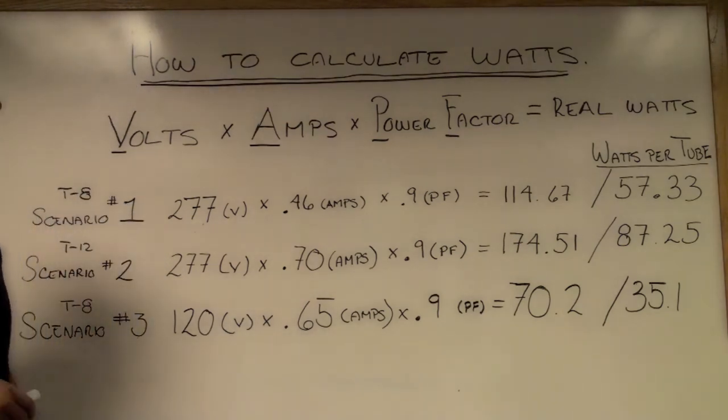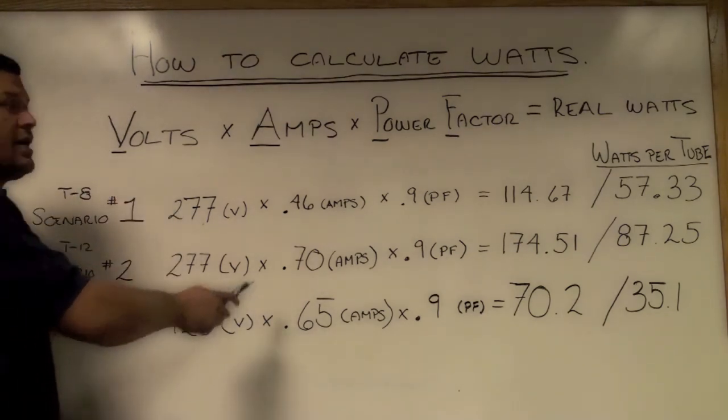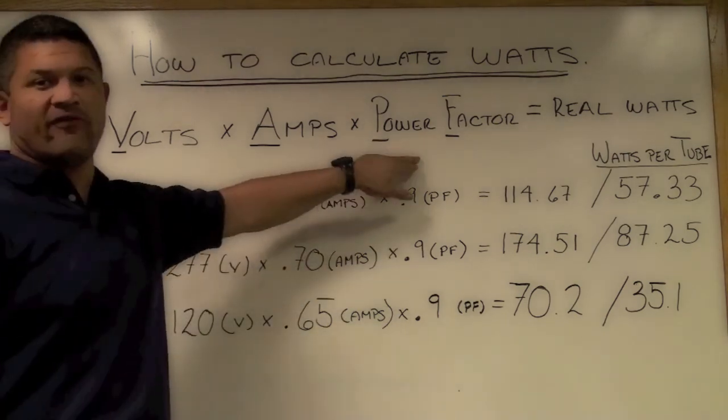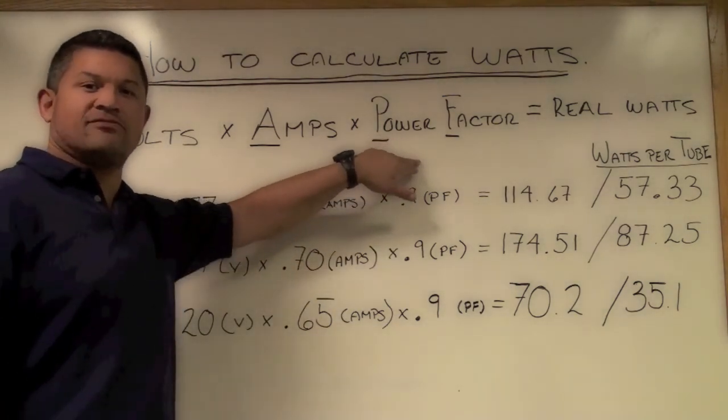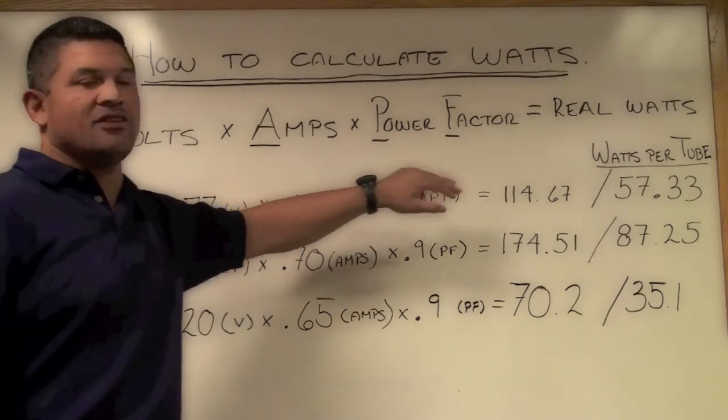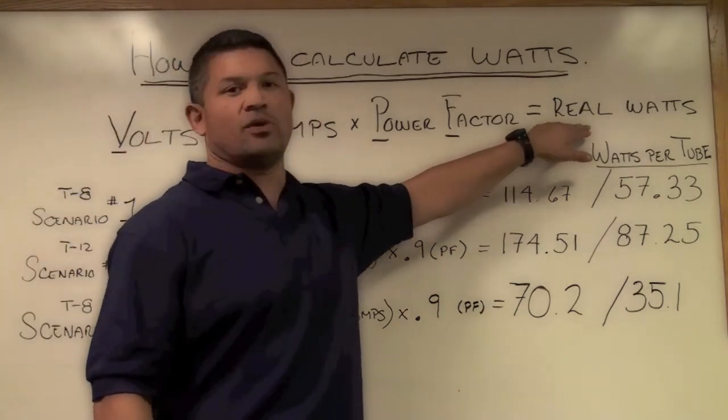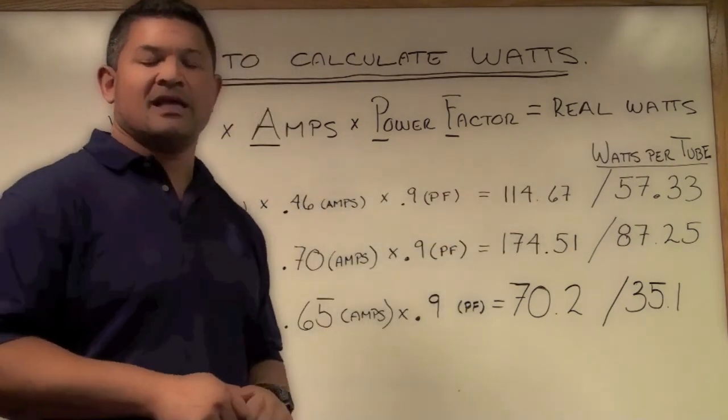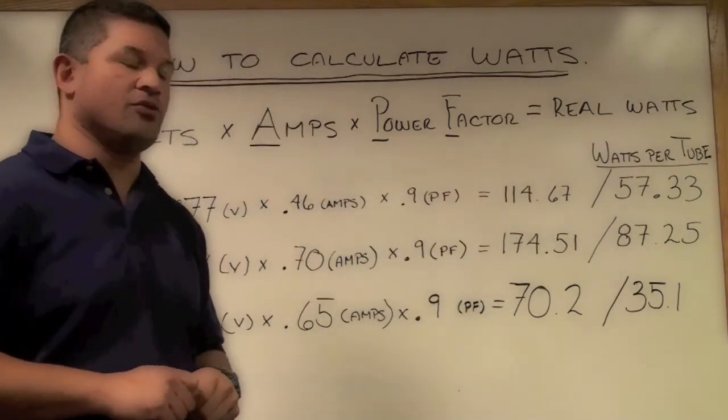What we're going to use as a calculation is volts times amps times power factor. We're going to default to 0.9 which is a commercial grade power factor. That will give you your actual watts when divided by the number of tubes or LED lights that you have in the unit.